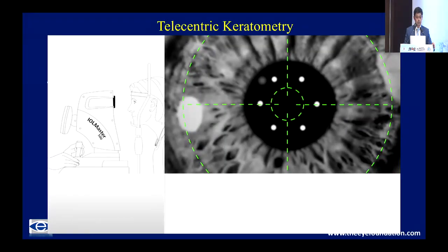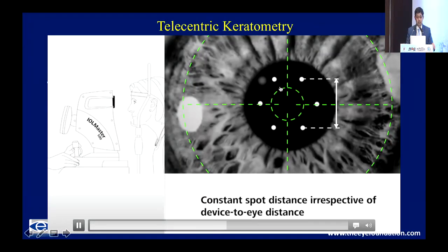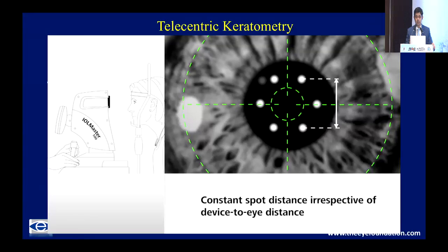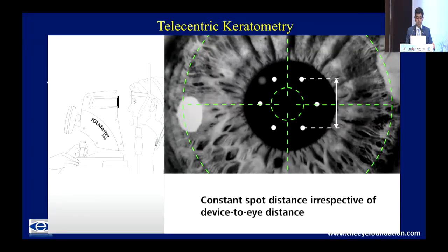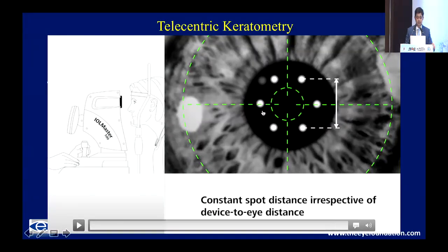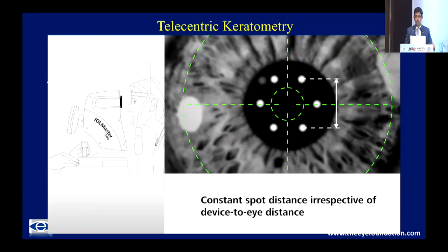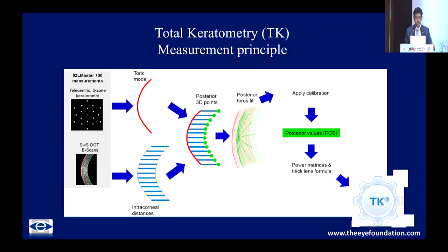Additionally, a concept like telecentric keratometry, especially in IOL Master, really helps, because even if the patient is not very cooperative or your biometrist is not as talented, it ensures that the spot spacing is kept the same irrespective of the device-to-eye distance. So this is very important because even if the patient is moving their head a little bit or is not rested completely, you still are measuring over the same region in the cornea and you get more repeatable values. That's one very important concept with telecentric.